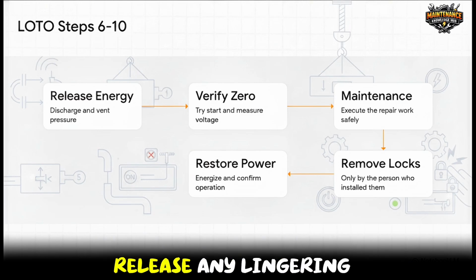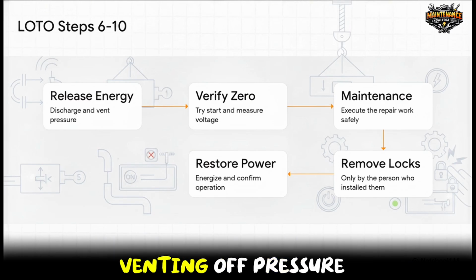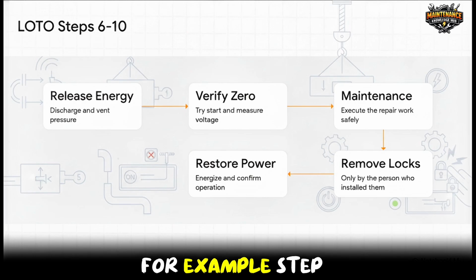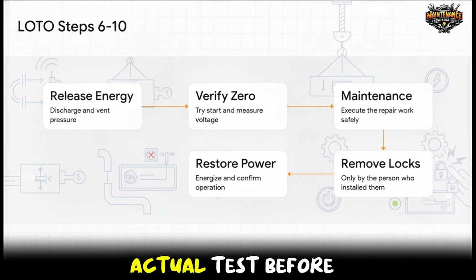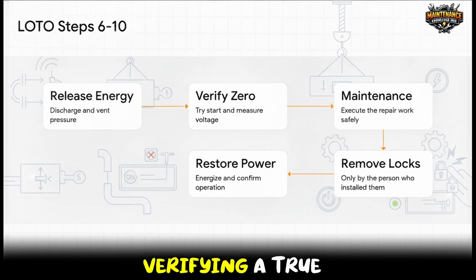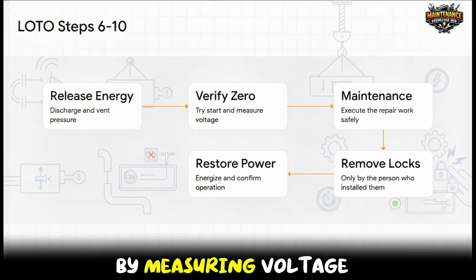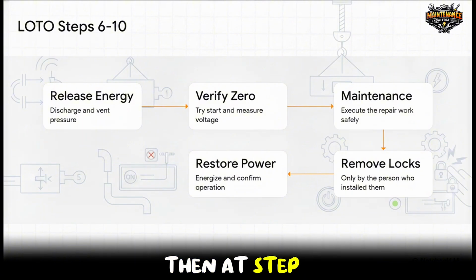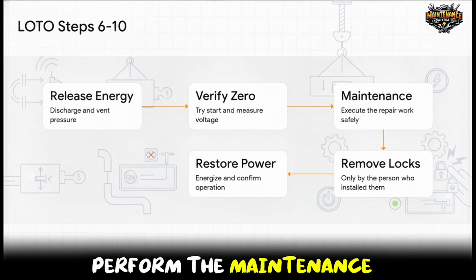Step 6: you release any lingering stored energy, venting off pressure or discharging capacitors, for example. Step 7 is the test before touch, verifying a true zero energy state by attempting a normal startup and double-checking by measuring voltage. Only then, at Step 8, can you actually perform the maintenance safely.